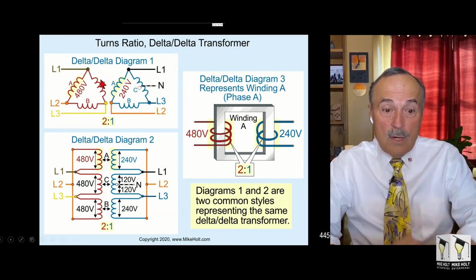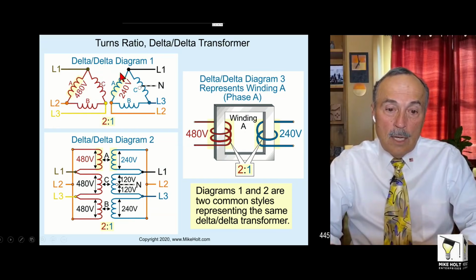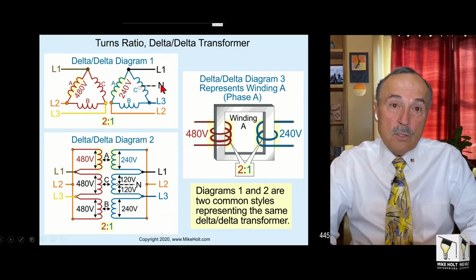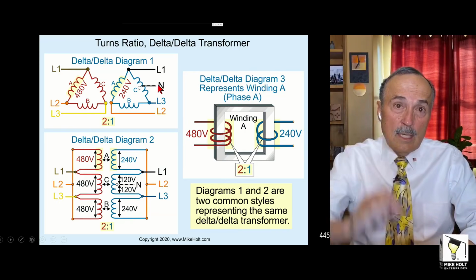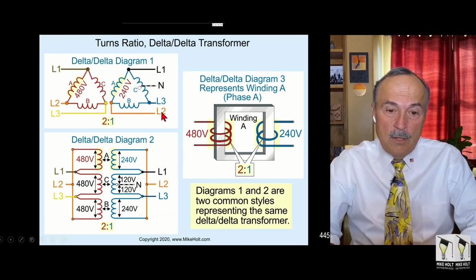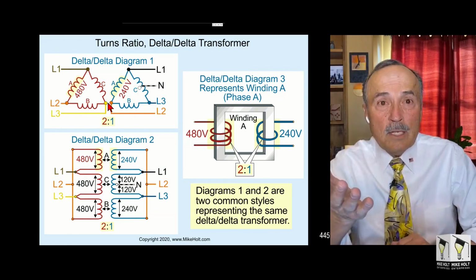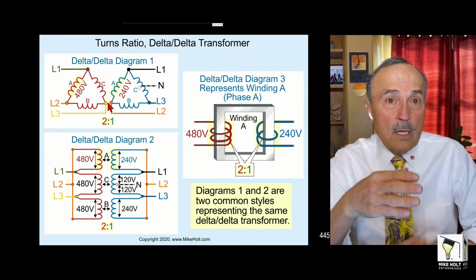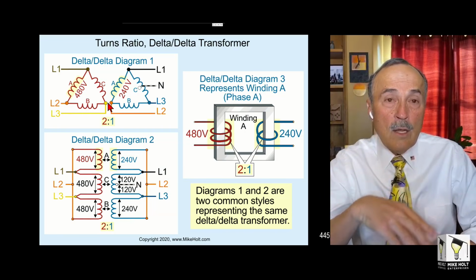Look at this configuration right here. Here's a delta secondary, and then the center point of that one winding, which means you have a neutral here. Anytime it's the center of a single winding, it's going to be the neutral. And you can see the high leg is all the way out here in line 2.